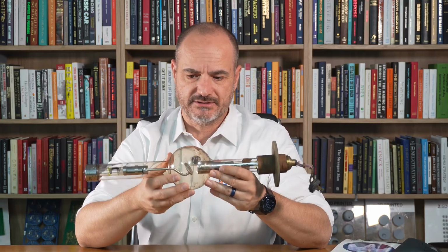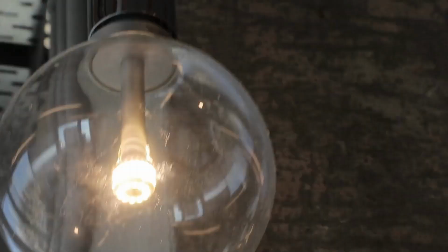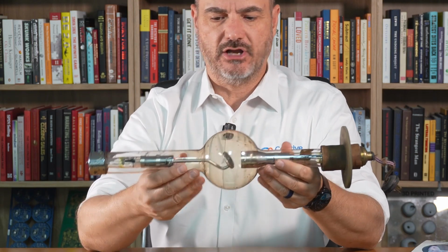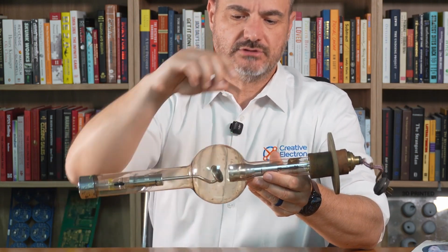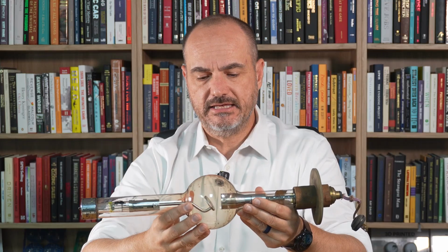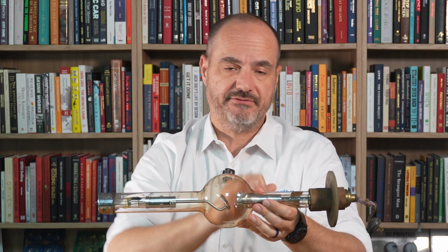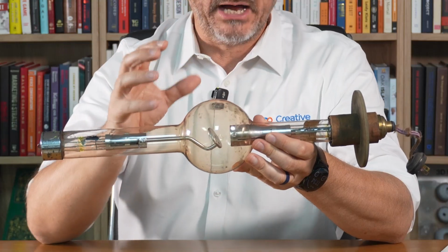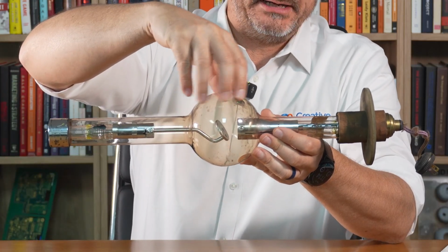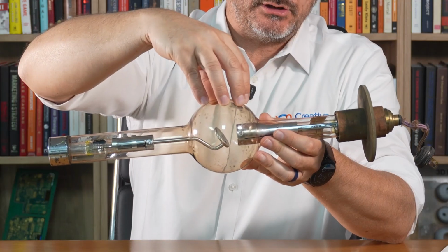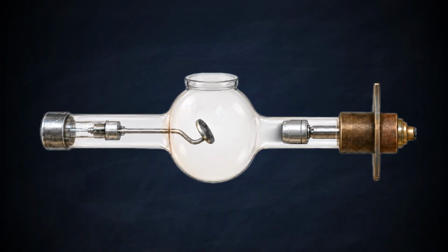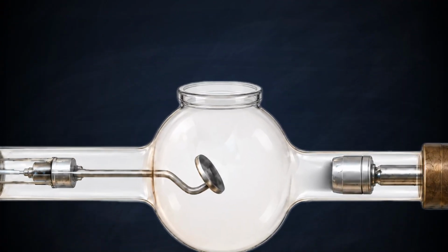But that's fundamentally what a sealed tube is, right? It looks like an old light bulb, right? It's a light bulb, but that's the technology. You have a vacuum sealed filament and target. The open tube, on the other hand, is a similar concept. You still have a filament, you still have a target, but you have the ability to open this vacuum enclosure and replace the filament as needed, which is great, right?